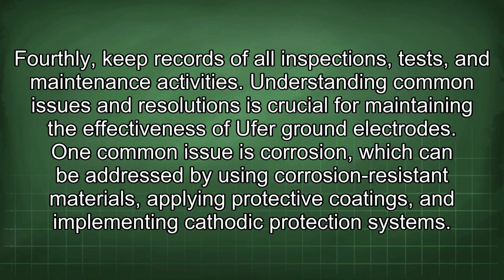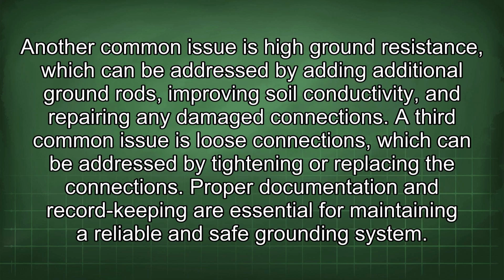Understanding common issues and resolutions is crucial for maintaining the effectiveness of Ufer ground electrodes. One common issue is corrosion, which can be addressed by using corrosion-resistant materials, applying protective coatings, and implementing cathodic protection systems. Another common issue is high ground resistance, which can be addressed by adding additional ground rods, improving soil conductivity, and repairing any damaged connections.